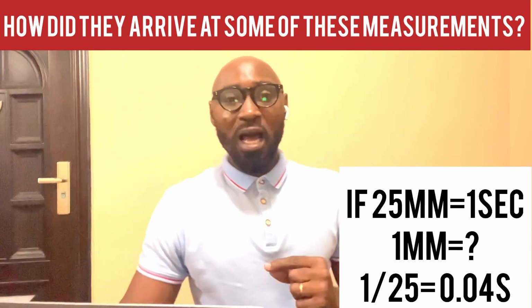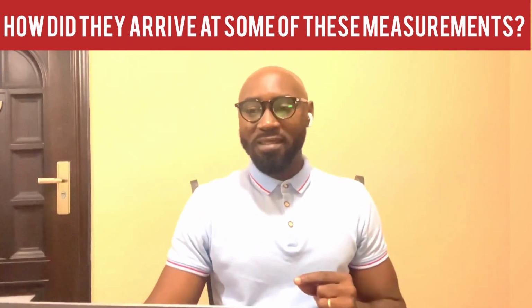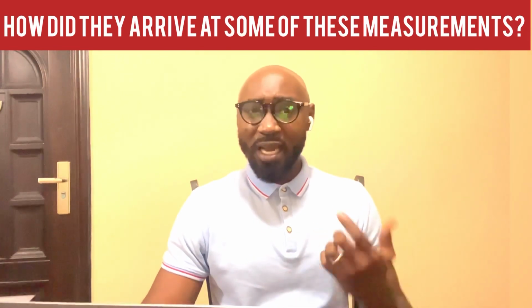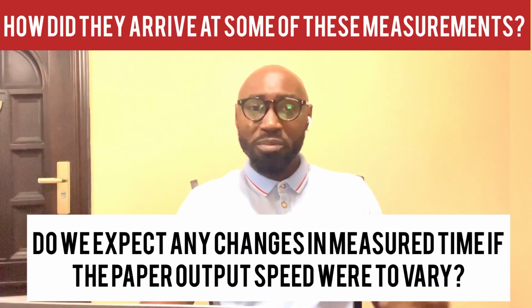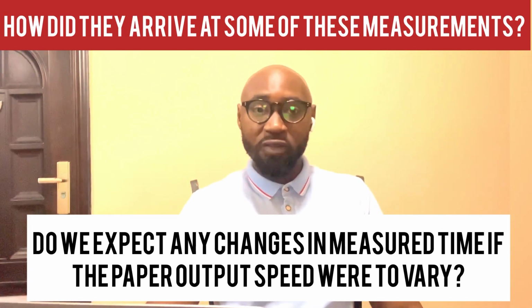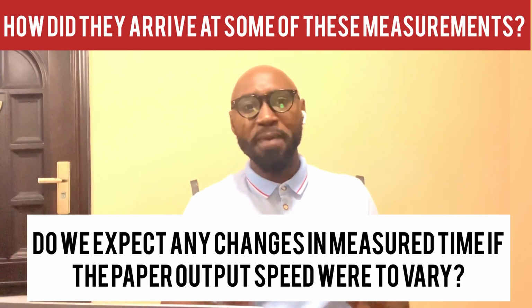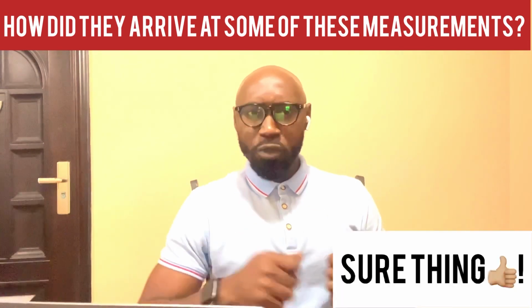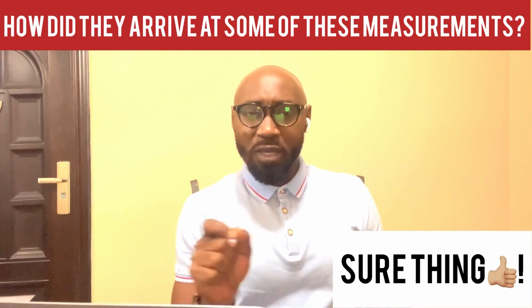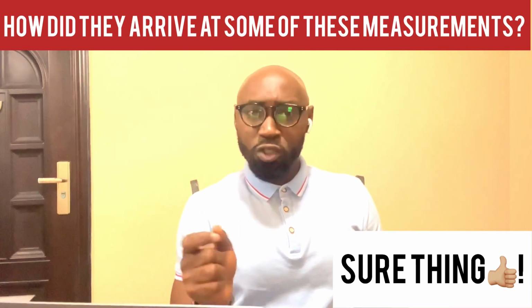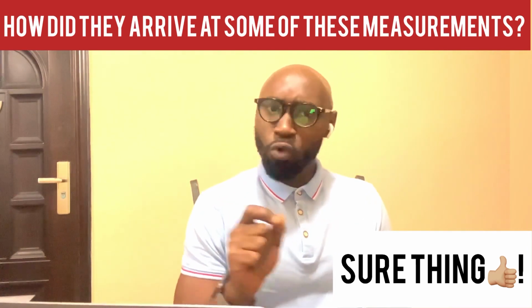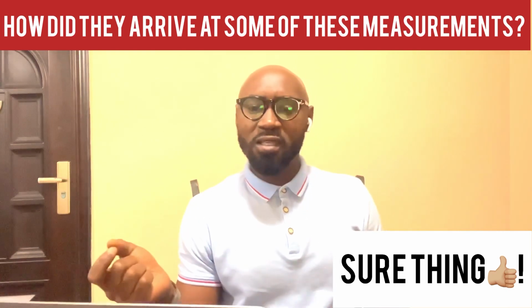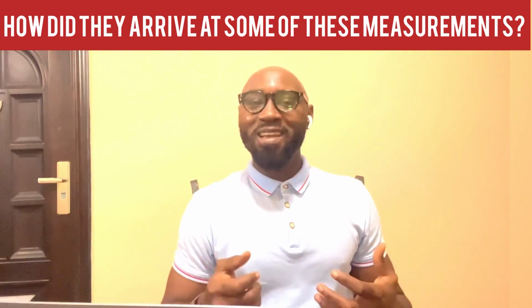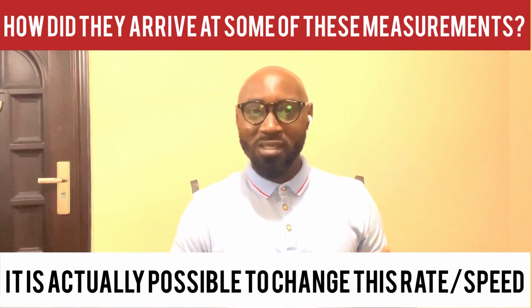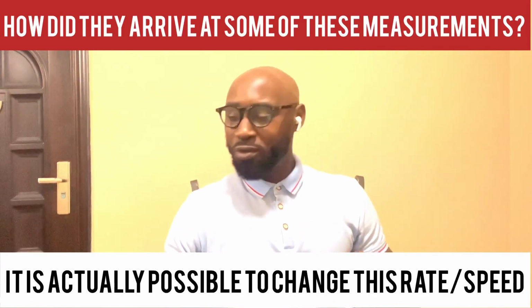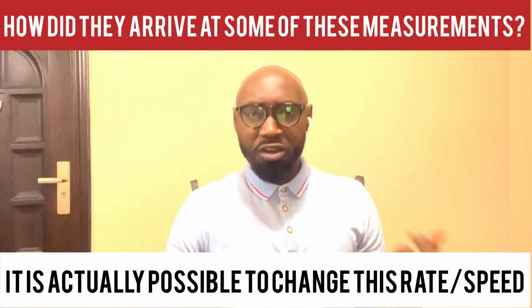Ladies and gentlemen, this then means that if the ECG were to record at any other speed, besides this 25 millimeters per second that we have just mentioned, then we also expect that the corresponding time measurements will also change, so that one small box will no more be equal to 0.04 seconds.